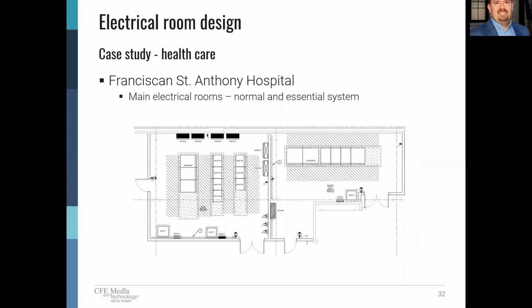So in the case of the main electrical rooms, we had the normal main electrical room and the essential system main electrical room. And as NFPA 110 requires, we have physical separation between those. So there's two distinct rooms. The room on the left contains the automatic transfer switch equipment. That's your EPS level 1 equipment that NFPA 110 requires to be separated from your normal service entrance equipment. This represents a very small fraction of the total distribution that was in this building, but it's a good example.